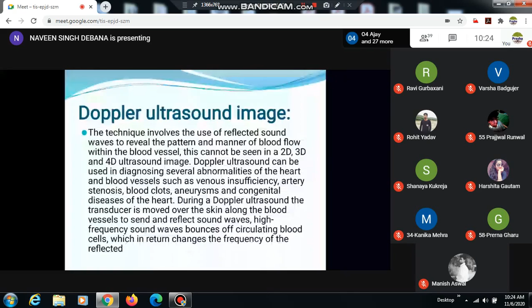During a Doppler ultrasound, the transducer is moved over the skin along the blood vessel to send reflected sound waves. High frequency sound waves bounce off circulating blood cells, which in return changes the frequency of the reflected wave, referred to as the Doppler effect. In the absence of blood flow, changes do not occur in the reflected sound wave. Data from the reflected sound wave of the Doppler effect is used to construct a graph representing the pattern and the manner of blood flow through the blood vessel on the CPU. There are different types of Doppler ultrasound, namely color Doppler, spectral Doppler, and power Doppler.